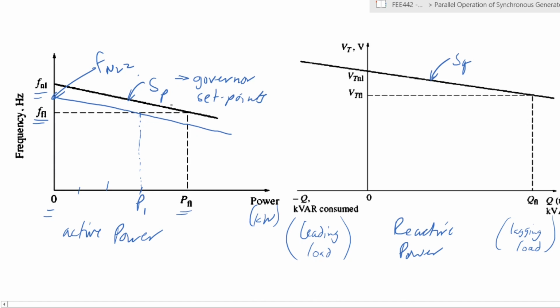Okay. So the governor set points that you put will determine if the load changes momentarily, very small load changes, they will change along this line. So the frequency will alter along this line. That is why if you stand next to a generator, for example, when it is first switched on and you have a load applied, you will hear the frequency of the sound dropping. It is an actual change because the governor is doing its job of changing the position of the frequency to match the load that is being supplied. However, if you have now longer term load requirements, that's when you can change the actual governor set points.